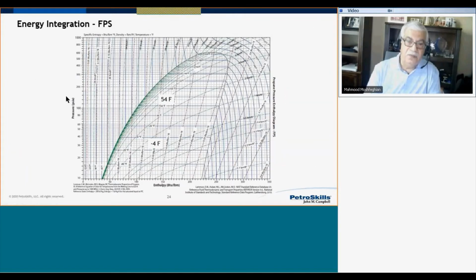I can use the pH diagram. This is the actual pH diagram. So my condensing temperature is 54 degrees Fahrenheit, and my chiller temperature is -4 degrees Fahrenheit as before. My chiller duty is the same as before, 8.1 million as well. So I draw a horizontal line. This is 60, this is 40 degrees Fahrenheit, this is 54, and I can read the condensing pressure, about 100 psi.